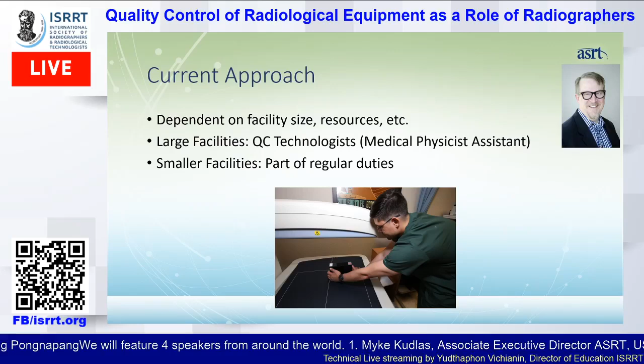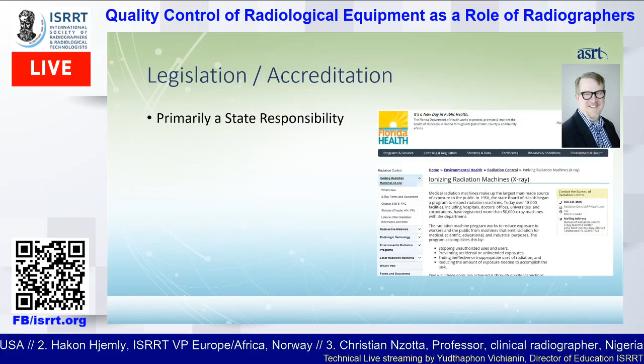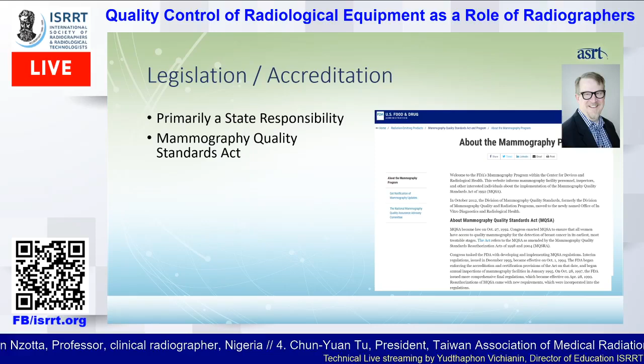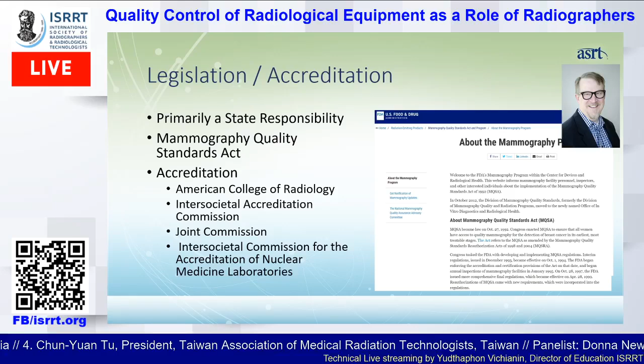So quality control legislation and accreditation is primarily a state responsibility. When I lived and worked in Florida, I was very well aware of the Florida Department of Health rules and regulations, and the state would actually come to our facility once a year and test our equipment in addition to what the medical physicist was doing or what I was doing. On a federal level, probably the biggest law from the FDA is the Mammography Quality Standards Act that focuses specifically on mammography. And once again, there'll be testing annually on a state level to make sure that we're adhering to the Mammography Quality Standards Act. Then beyond that are individual accreditors. Now most of these accreditors will follow what the state has to say or what MQSA has to say, but there could be a site visit from them as well.